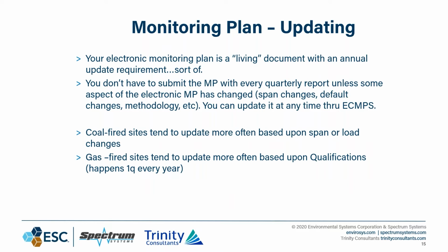Now, again, with talking about updating your monitoring plan, the electronic portion is a dynamic publication with sort of an annual update requirement. You don't have to submit your monitoring plan with every quarterly report like you used to in the flat file days, unless some aspect of the electronic portion has changed: changes to spans on your analyzers, default constant changes, monitoring methodologies. You can update it anytime through the portal, through the reporting platform.